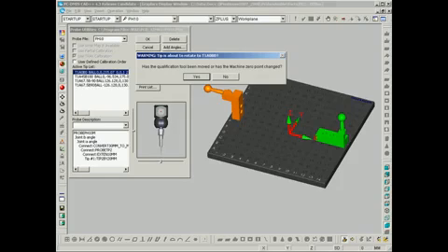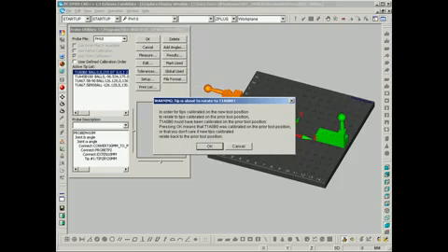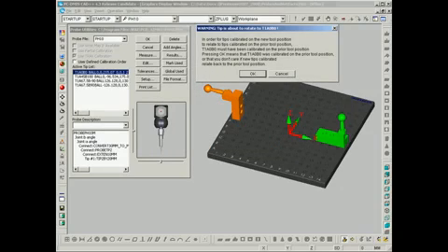Now, this is what this dialog means. In order for tips calibrated on the new tool position to relate to tips calibrated on the prior tool position, T1A0B0 must have been calibrated on the prior tool position. And we've just done that. So this is the dialog that creates that relationship, or at least affirms the creation of the relationship between the green sphere and the orange sphere. We'll just select OK here.